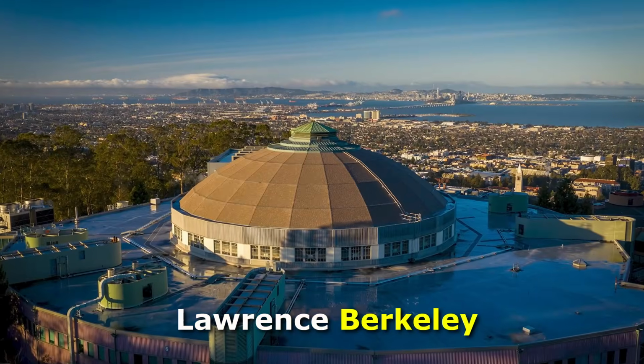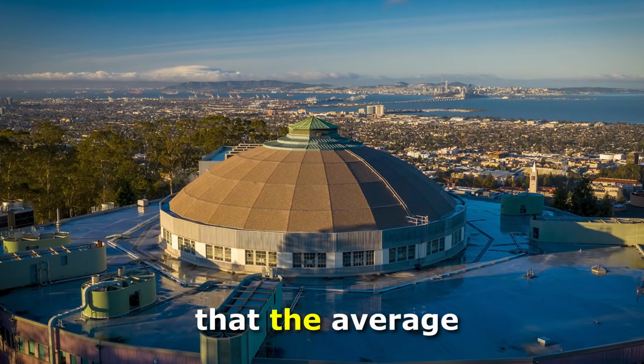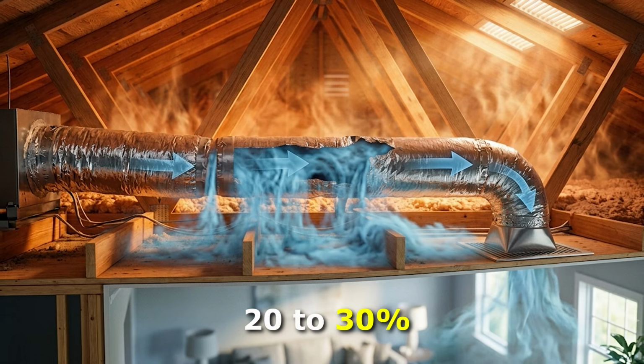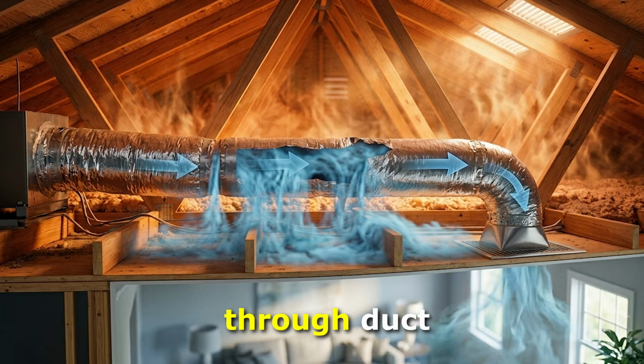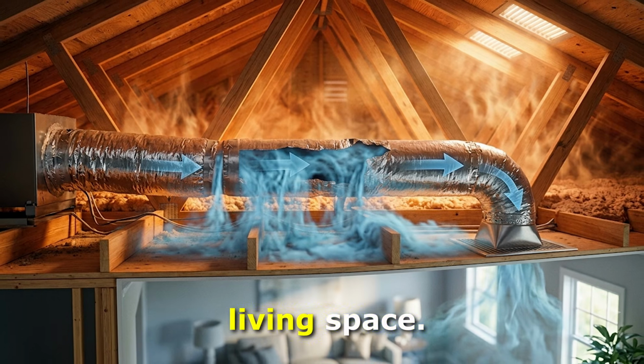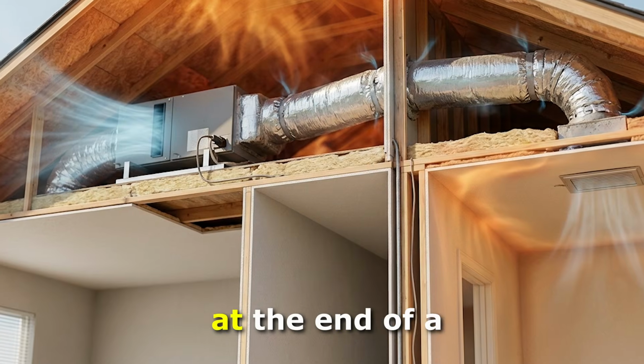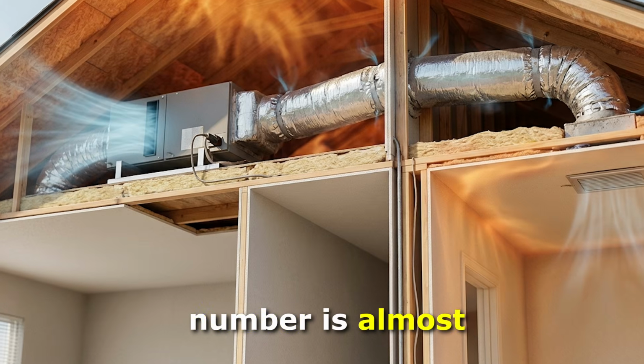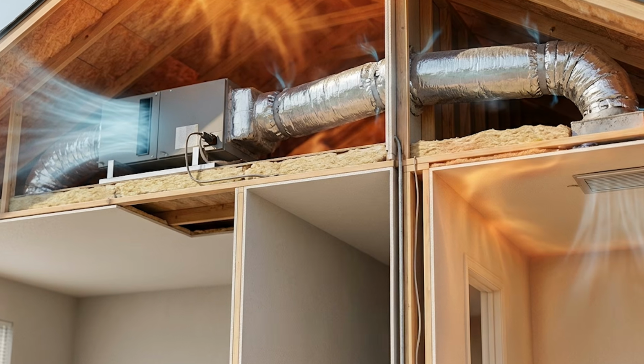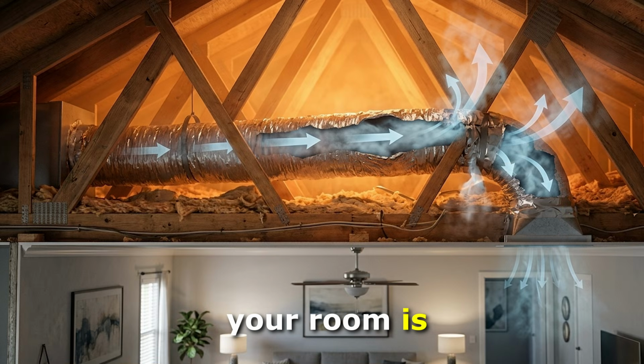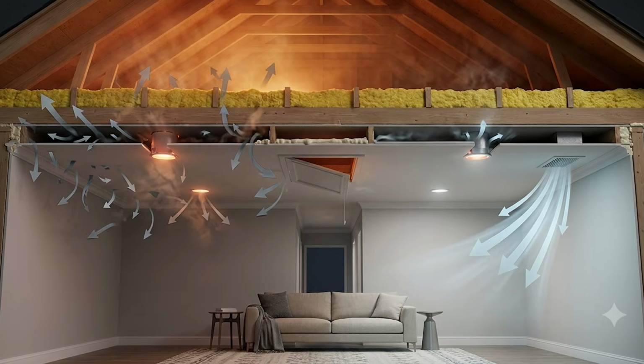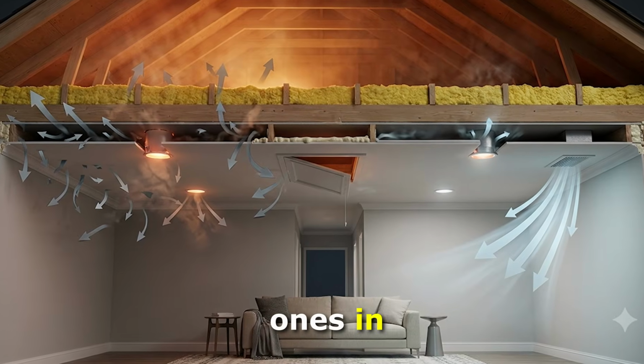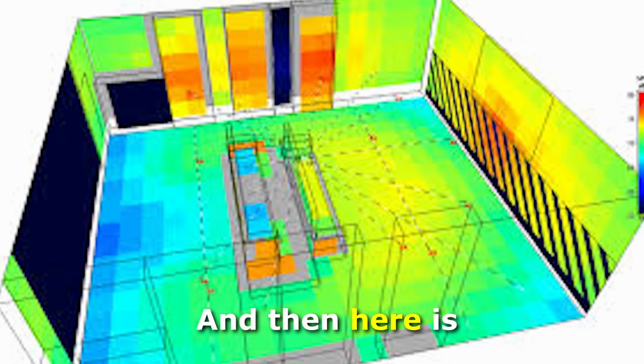Studies by Lawrence Berkeley National Laboratory found that the average home loses 20 to 30% of its conditioned air through duct leaks before it ever reaches the living space, and in a hot room at the end of a duct run, that number is almost always worse than average. The air that should be cooling your room is cooling your attic instead. Now you know where the gaps are. Here is how to find the specific ones in your house. And then here is the fix.